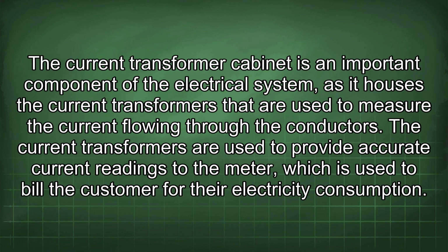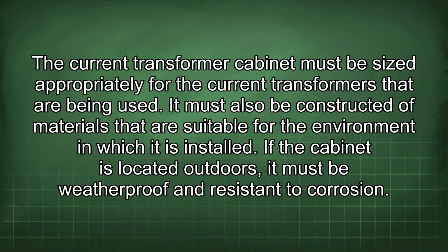The current transformer cabinet is an important component of the electrical system, as it houses the current transformers that are used to measure the current flowing through the conductors. The current transformers are used to provide accurate current readings to the meter, which is used to bill the customer for their electricity consumption. The current transformer cabinet must be sized appropriately for the current transformers that are being used. It must also be constructed of materials that are suitable for the environment in which it is installed. If the cabinet is located outdoors, it must be weatherproof and resistant to corrosion.